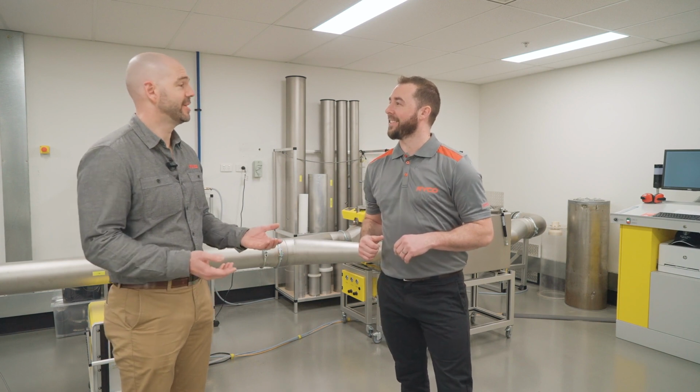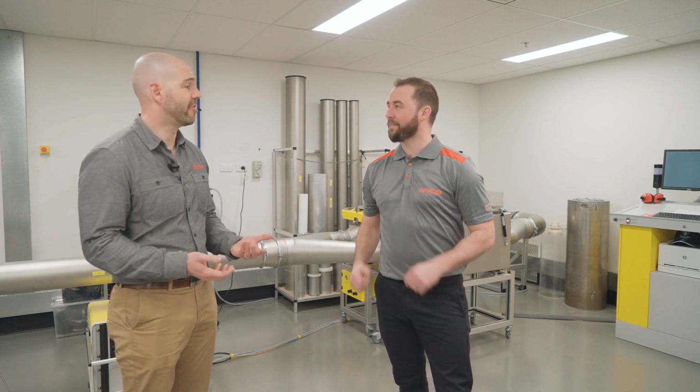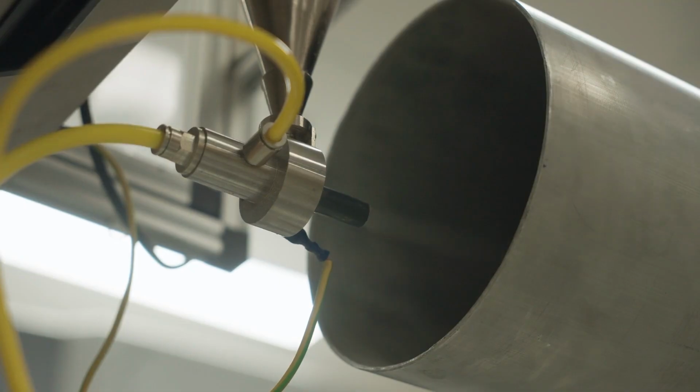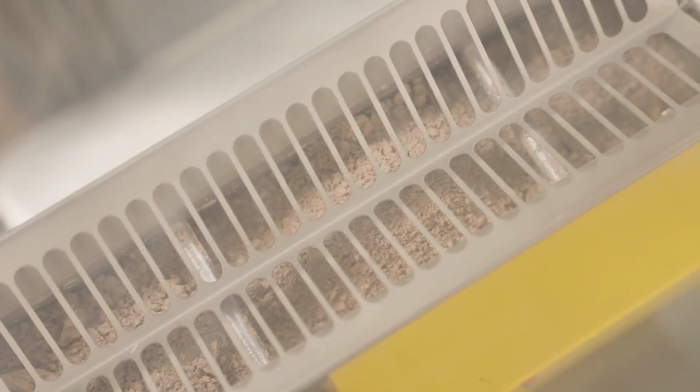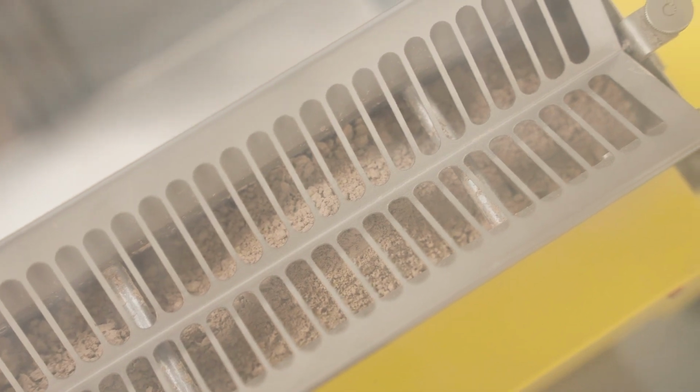Well, as you know, Australia is a very dry, dusty place. We have some of the finest dust in the world. So in the ISO test, we get the option to use fine dust or coarse dust. Now, because we want to make sure that our testing is representative of what our customers experience, we opt to use fine dust because that better represents what we see in Australia. That fine dust actually comes from Arizona, but it's prescribed by the ISO standard.